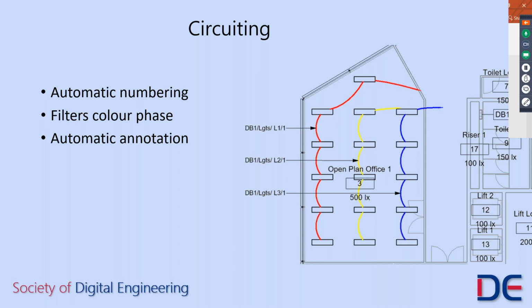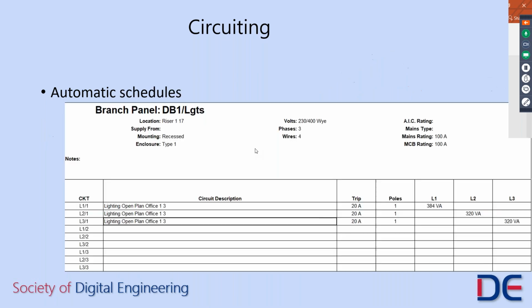But this also gives us a very, very quick identification as to which phase each of those lighting circuits is on. And what I've done here is I've actually used a colour filter to measure the phase of each circuit. And as we can see, we're using three different phases in a space, which isn't necessarily a great idea because you can actually get a three-phase shock if you touch two of those live cables. And we don't want to do that because that is actually hazardous to life. Also, we're using automatic annotation. So here, I'm actually automating the tagging of each circuit, and I'll go into that in a little bit more detail now. We can also create a panel schedule, and this is just another view of the same data.